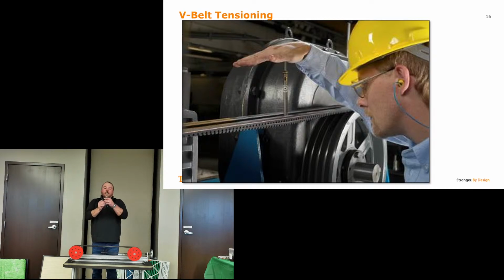All right, and then I'm going to take my measurement, and I am right at 7.5 pounds of force. Okay? So is 7.5 pounds of force good or bad? That's when I reference my table. So first column says gold ribbon cog belt. So I am using a BX series belt. So I will be in the second set of 4, second one down, BX.